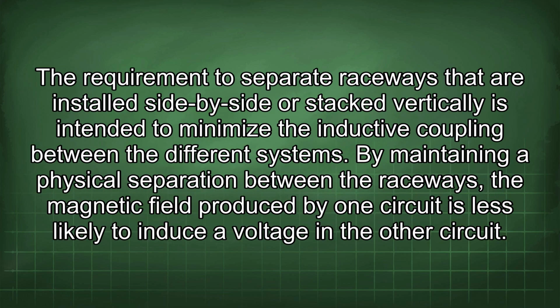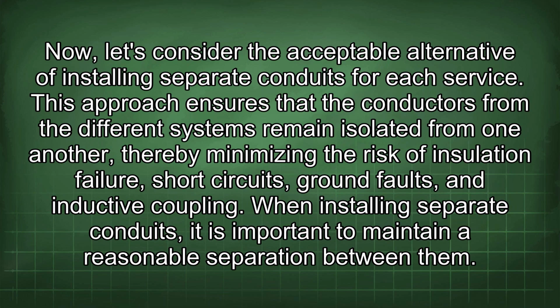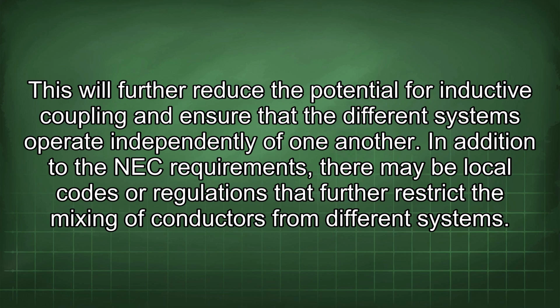The requirement to separate raceways that are installed side by side or stacked vertically is intended to minimize the inductive coupling between the different systems. By maintaining a physical separation between the raceways, the magnetic field produced by one circuit is less likely to induce a voltage in the other circuit. Now, let's consider the acceptable alternative of installing separate conduits for each service. This approach ensures that the conductors from the different systems remain isolated from one another, thereby minimizing the risk of insulation failure, short circuits, ground faults, and inductive coupling. When installing separate conduits, it is important to maintain a reasonable separation between them. This will further reduce the potential for inductive coupling and ensure that the different systems operate independently of one another.